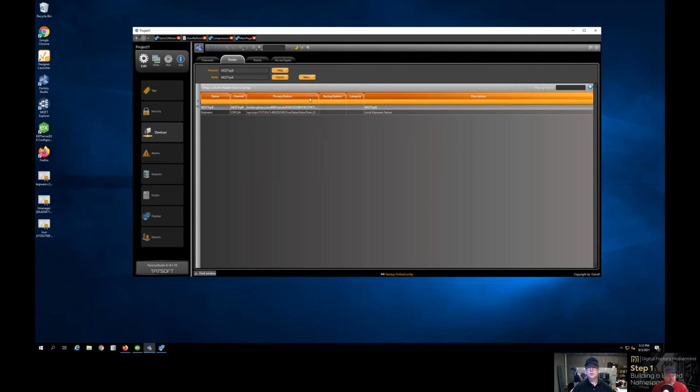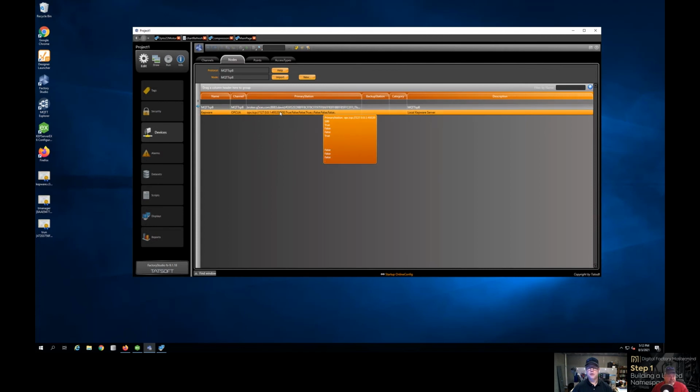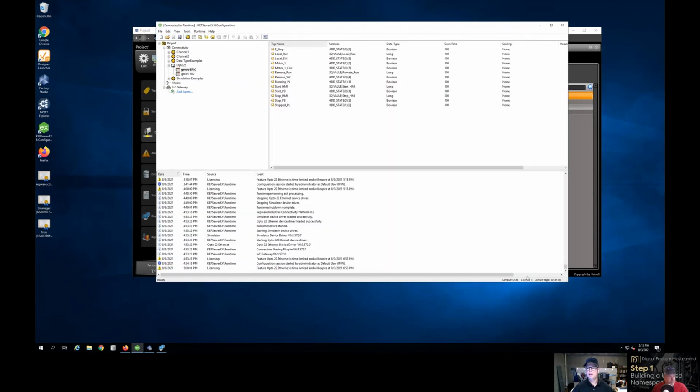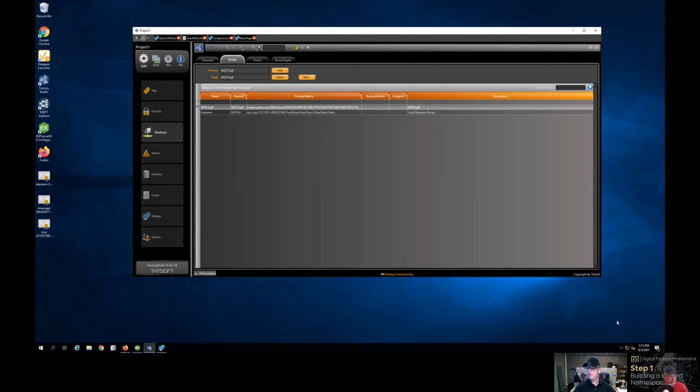This is where you get into your primary station and go through all the configuration of that. Now, one thing I want to caution people with FactoryStudio out of the box, on the current version 9.1.8, is that when you go in and configure your OPC server, you're going to have to create some certificates. If you look over here on my desktop, there is a runtime, and there's also just a manager tag. That's a server certificate that you have to create, and you have to bring those over into Kepware as well.